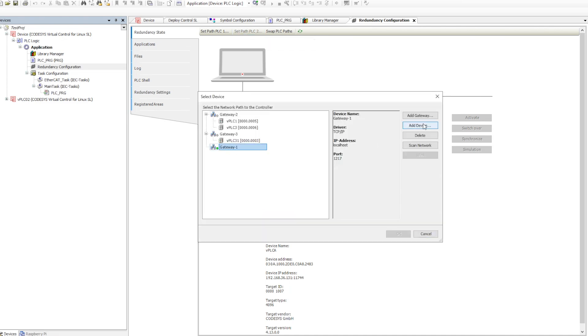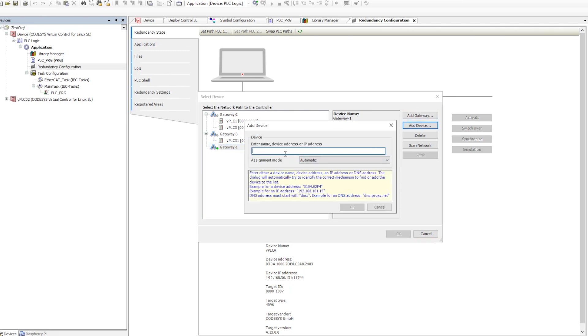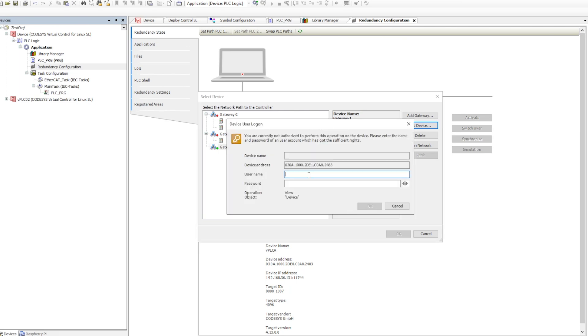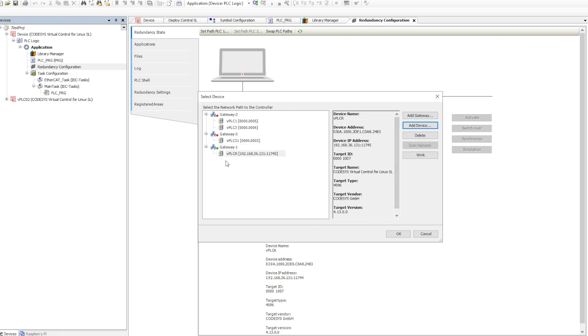The second PLC we need to configure manually, so I'm going to add that device. Since I'm using a virtual PLC, I'm just typing the device IP and then giving the port number. The reason for the port number is that I am accessing all those PLCs from my local system — localhost is trying to connect — so with port-based access we can access the virtual PLCs.